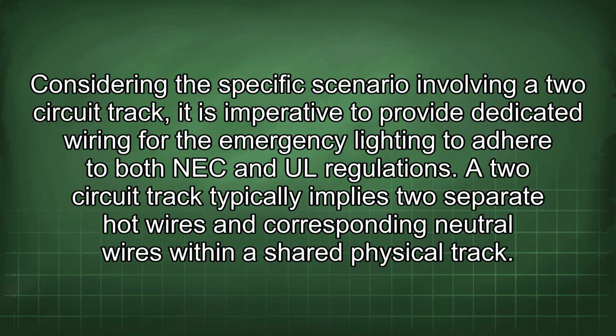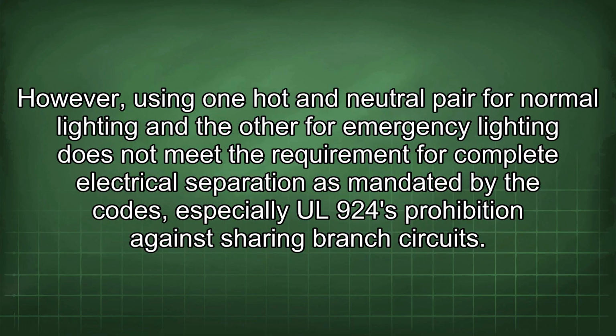Also, local electrical codes can vary, so checking with the local authority is recommended. Considering the specific scenario involving a 2-circuit track, it is imperative to provide dedicated wiring for the emergency lighting to adhere to both NEC and UL regulations. A 2-circuit track typically implies 2 separate hot wires and corresponding neutral wires within a shared physical track. However, using one hot and neutral pair for normal lighting and the other for emergency lighting does not meet the requirement for complete electrical separation as mandated by the codes, especially UL 924's prohibition against sharing branch circuits.